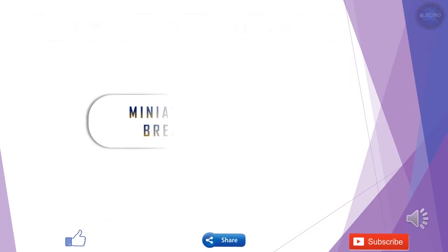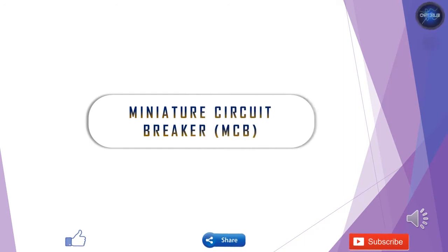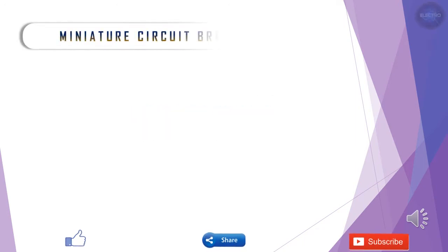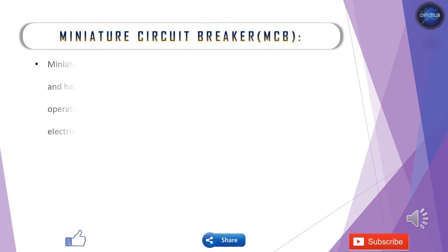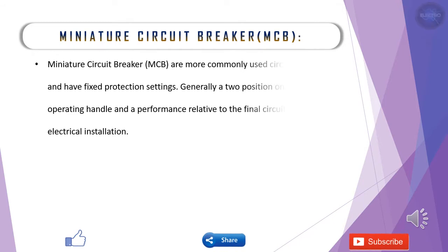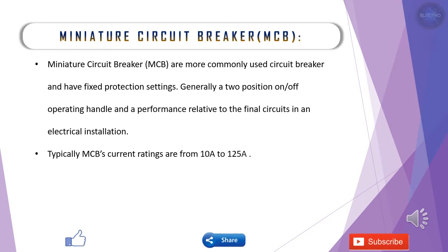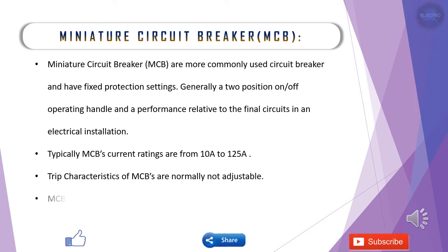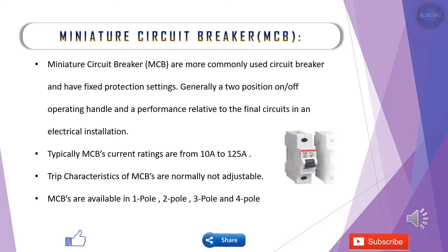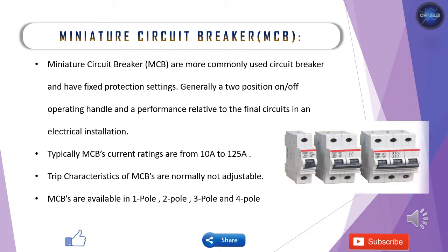Now we'll move to miniature circuit breakers — MCBs. These are the most commonly used circuit breakers in our daily life. They have a fixed protection type of settings only, generally a two-position on/off handle. MCBs are installed in our final circuits. The general ratings of MCBs range from 10 amps to 125 amps, and they are available in single pole, two pole, three pole, and four pole versions.